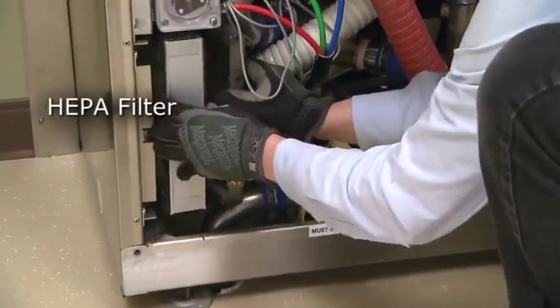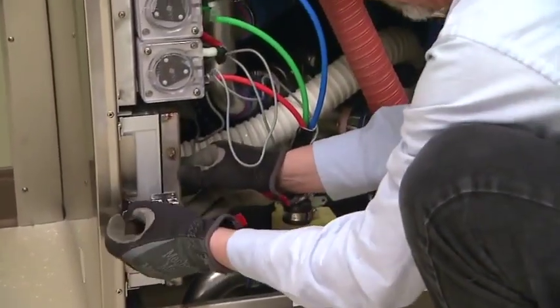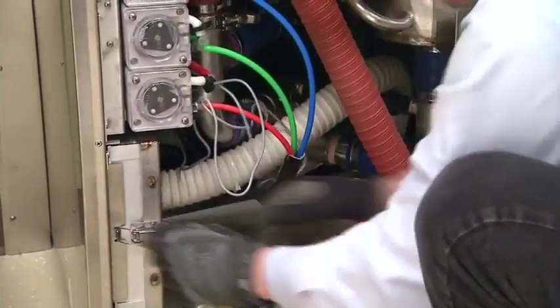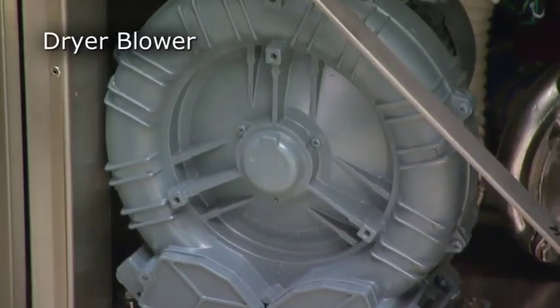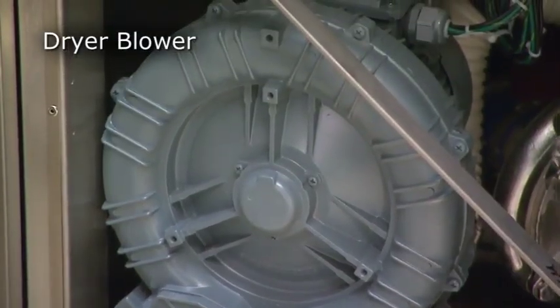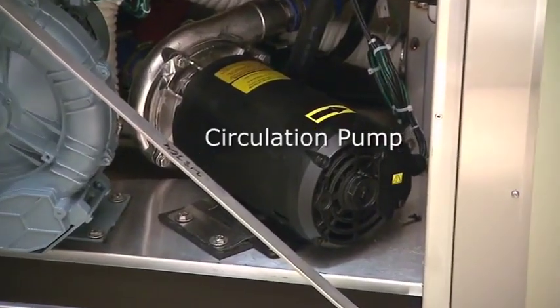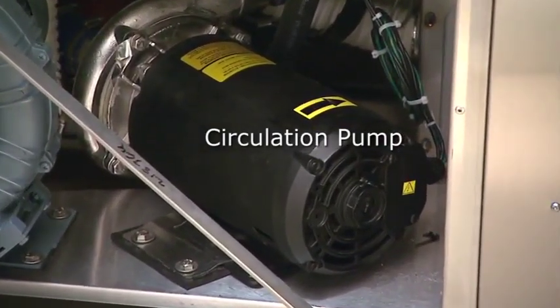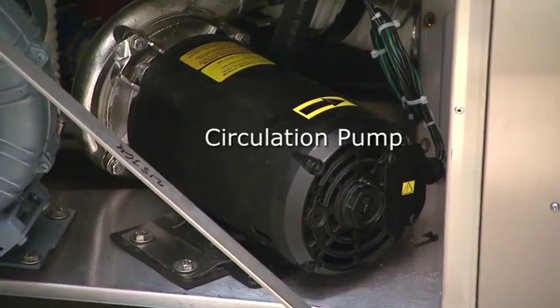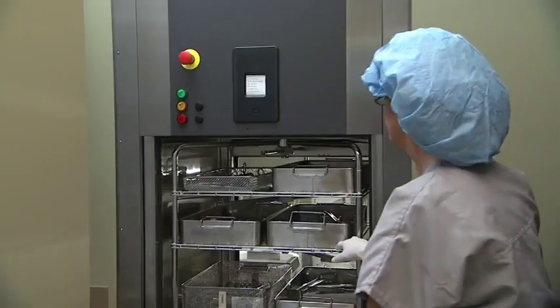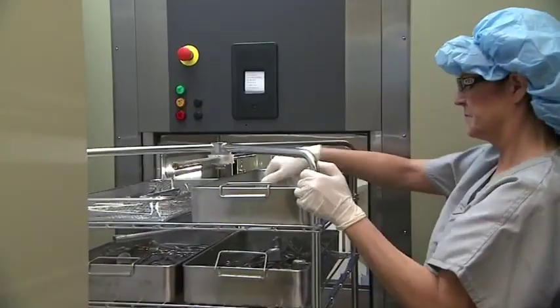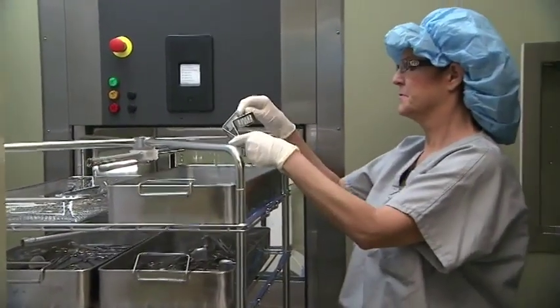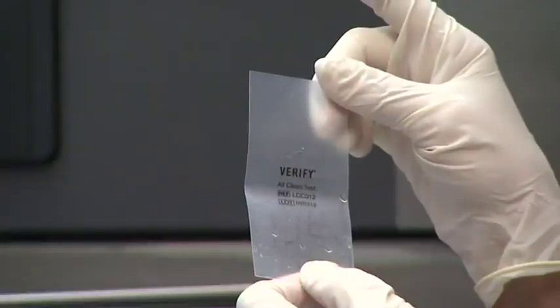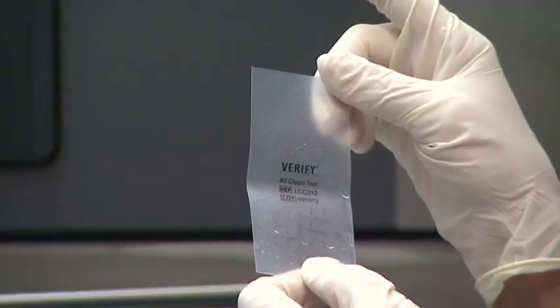A HEPA filter, shown here, filters incoming air to prevent contamination of the load. On the unload side, the dryer blower helps to dry the load and remove moisture from the air in the chamber. And the circulation pump assists in circulating water through the recirculation piping and the spray arms. Professional standards organizations recognize the importance of monitoring your mechanical and chemical cleaning process. STERIS recommends using the Verify All Clean Test Washer indicator on a daily basis.